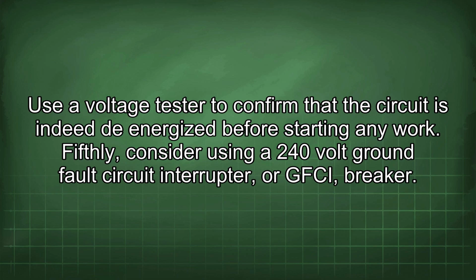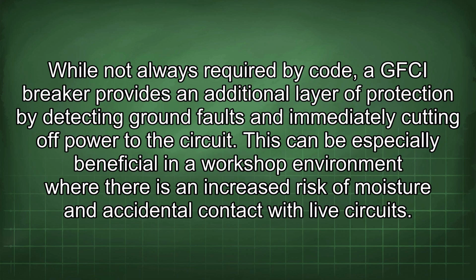Fifthly, consider using a 240-volt ground fault circuit interrupter, or GFCI, breaker. While not always required by code, a GFCI breaker provides an additional layer of protection by detecting ground faults and immediately cutting off power to the circuit.